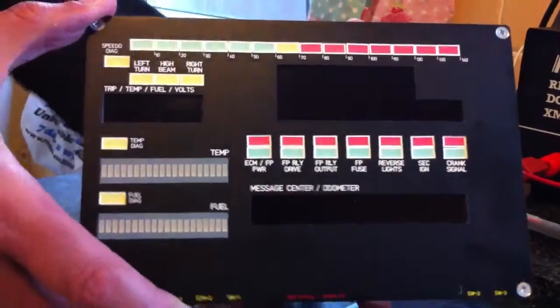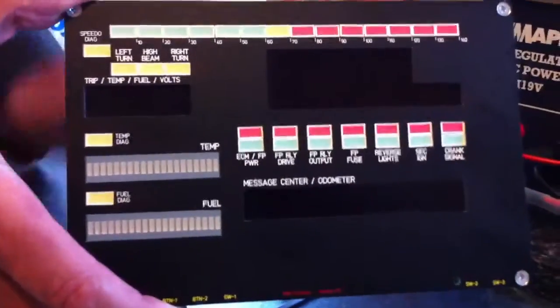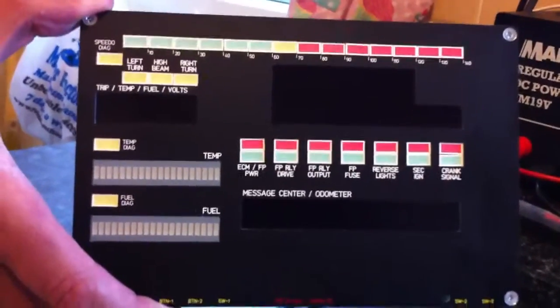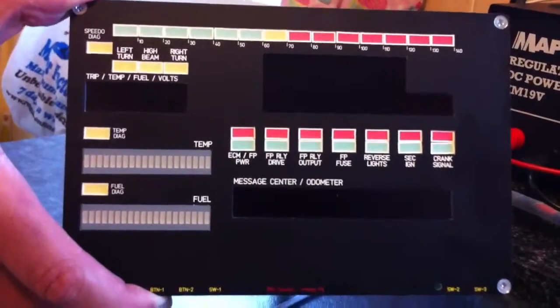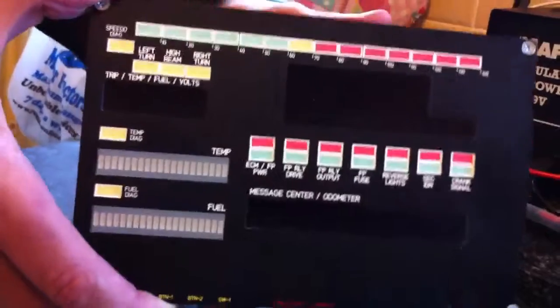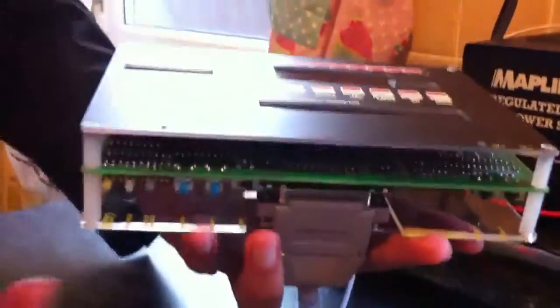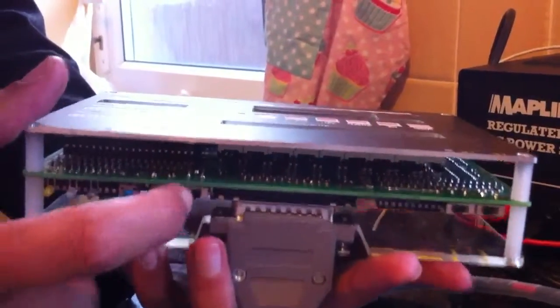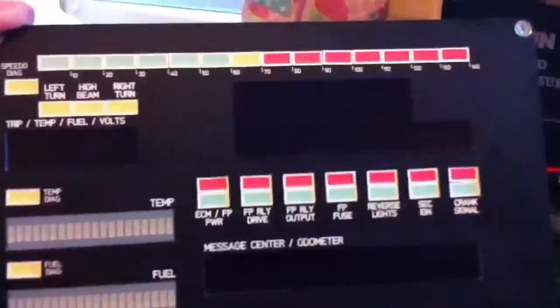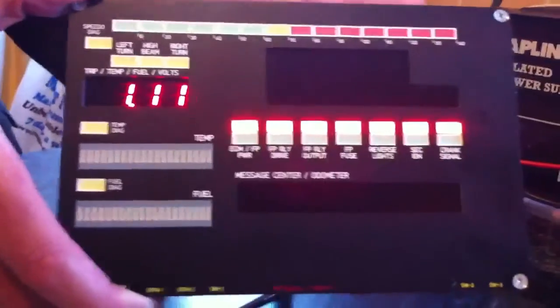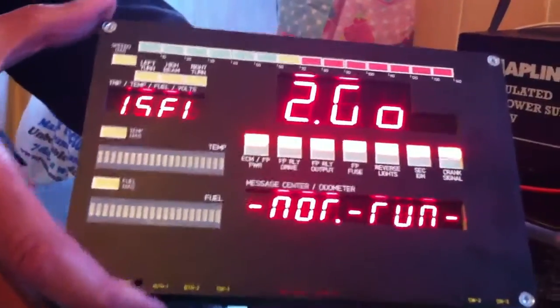Okay, options set mode. As you know, there are a number of different options that can be set on this unit, and we set the desired options using the options set mode. So as for all the modes except normal running mode, we need to make sure that switch number 1 is in the on position, which is to the right, so that when we apply power to the module, it powers up in operating mode select menu.